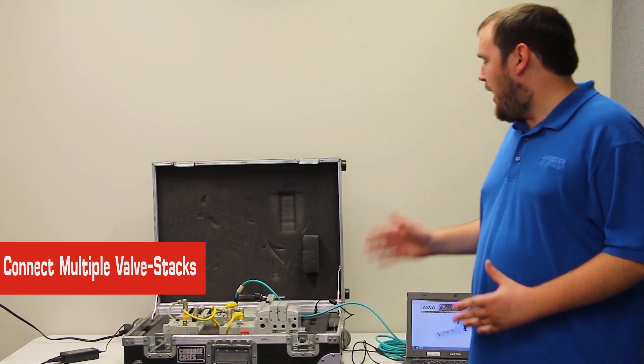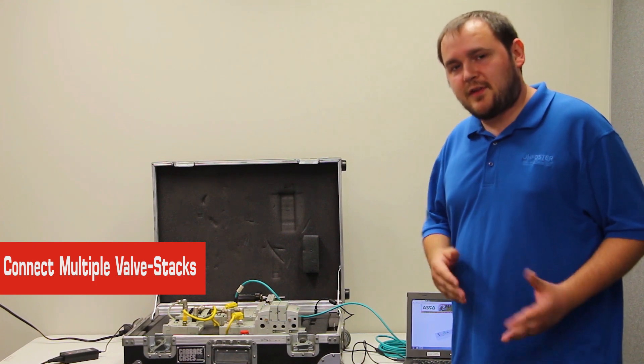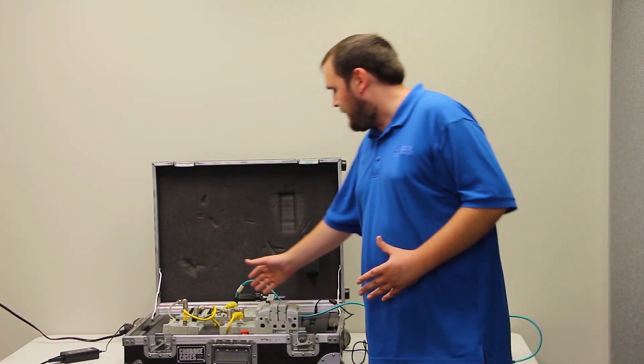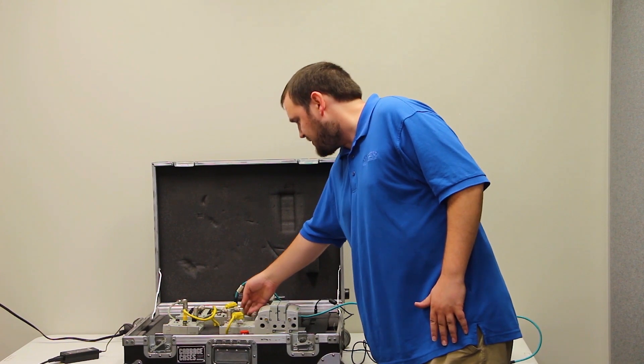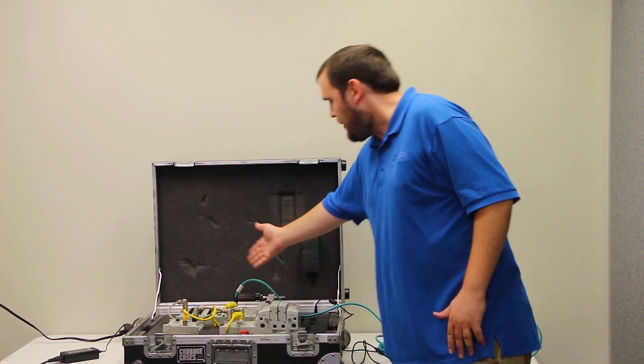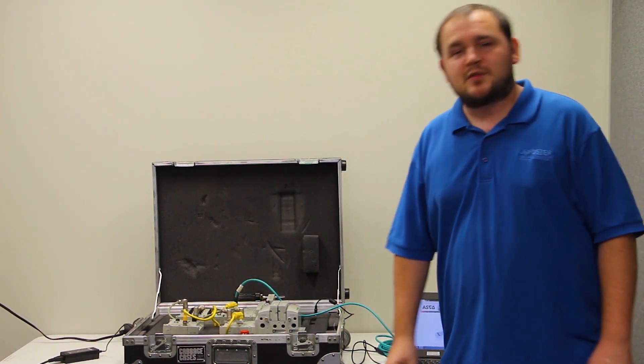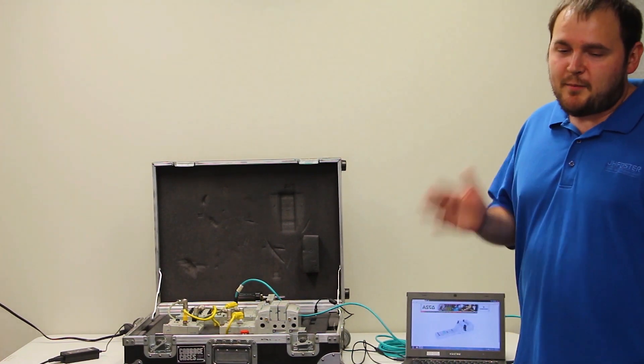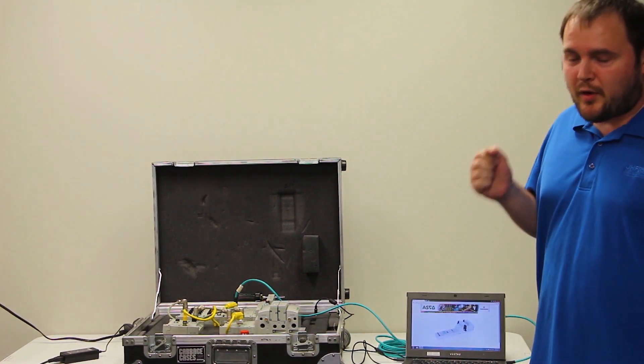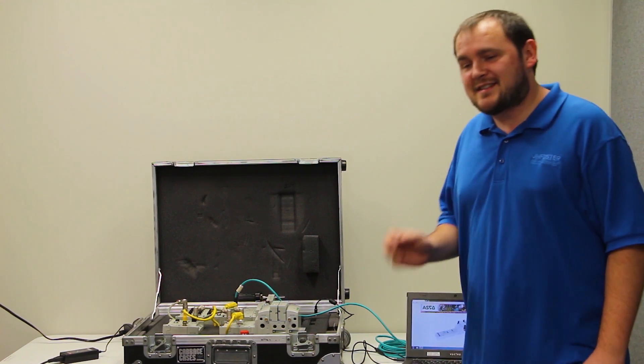So you do not have to wire each of your valve stacks individually to your PLC. They can all be connected to the main field bus, and then from the field bus you can go straight from your Ethernet cable into your PLC. So it makes wiring up your valve banks very quickly. You only have to worry about programming it to your PLC.